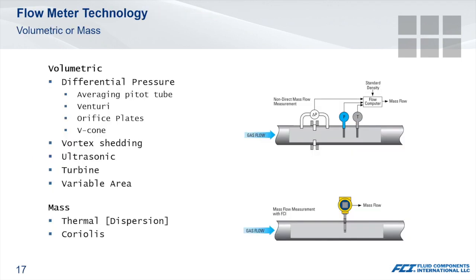Most gas flow meter technologies are volumetric. This may not be a concern for general monitoring of gases, but when there is interest in knowing the mass of a gas for stoichiometric purposes or production capacity, they fall short. Hydrogen requires 3 times the volume of natural gas for the same heating value, so knowing the mass flow of a pressurized gas system is important.